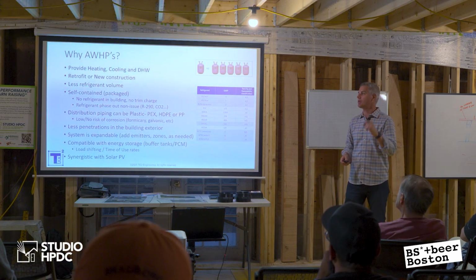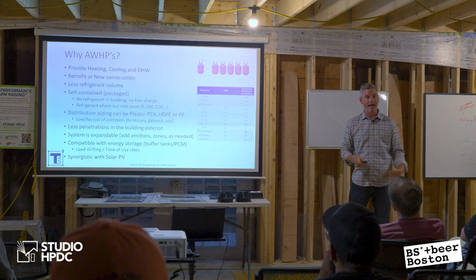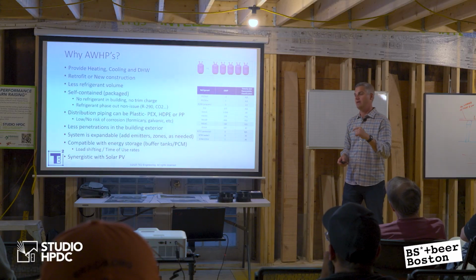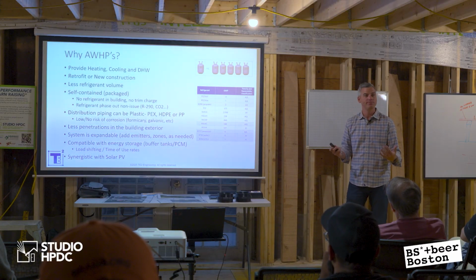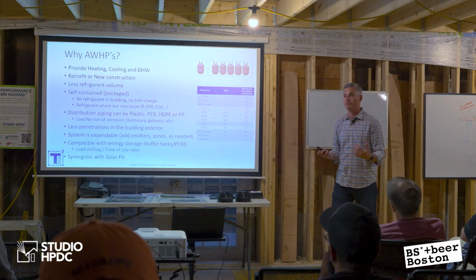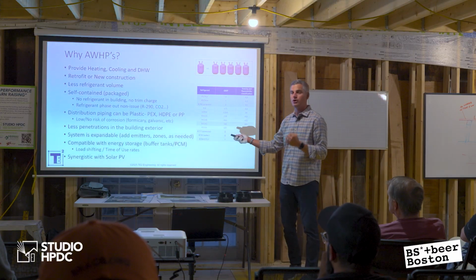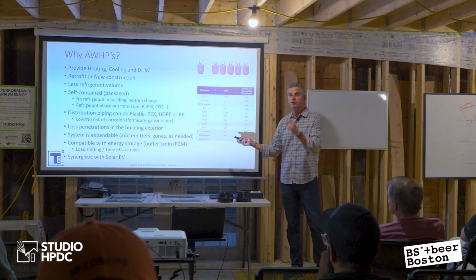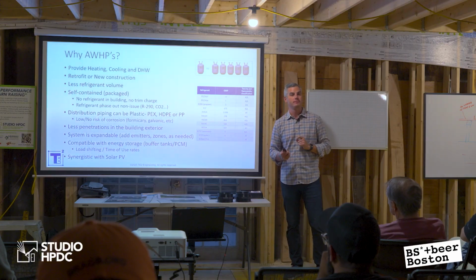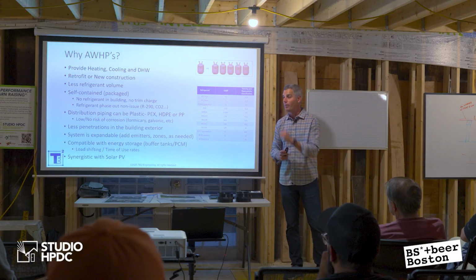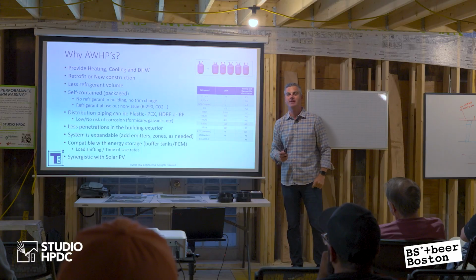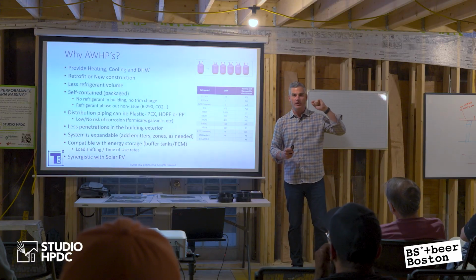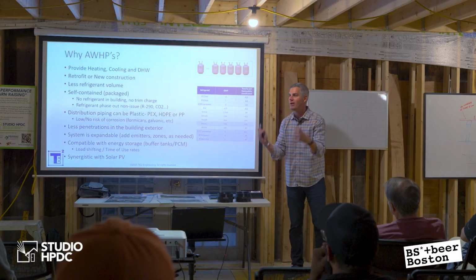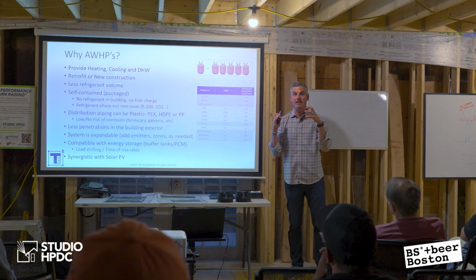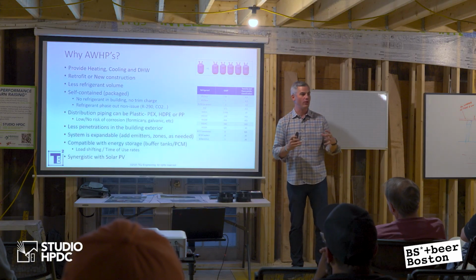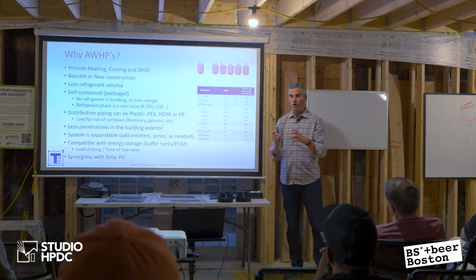I can't tell you how many times I go to an HVAC job that's gone bad, and it's because a flare fitting has failed and it's lost all its refrigerant, right? Or a big part of its refrigerant, right? So I don't have trim charge with air-to-water heat pumps. There is no trim charge. I don't even have to touch the refrigerant. I don't even have to bring out gauges. When you buy a refrigerator and you call the refrigeration technician to come fix it, it comes pre-packaged from the factory, hermetically sealed. That's the same thing with air-to-water heat pumps. Packaged. All comes from the factory.